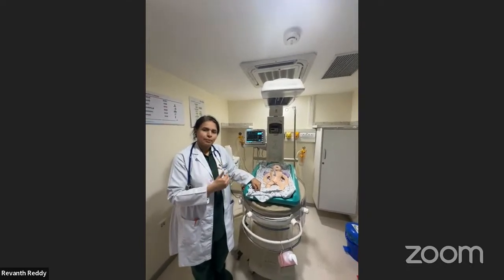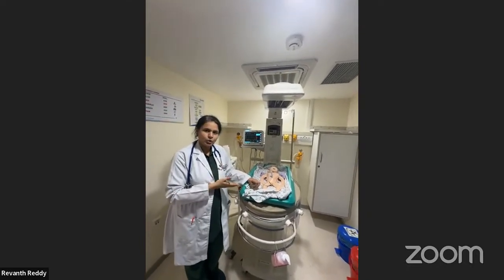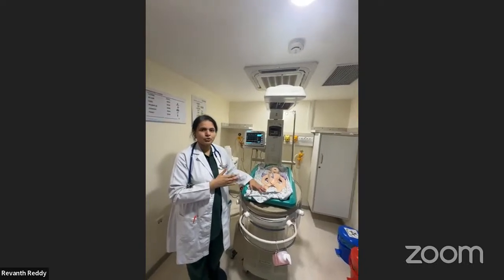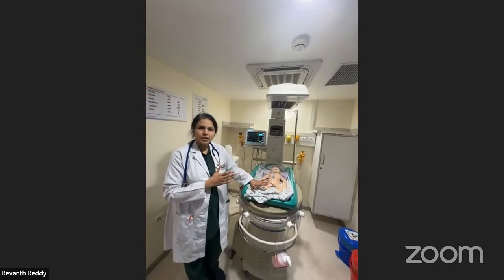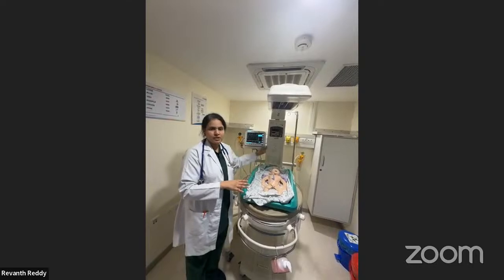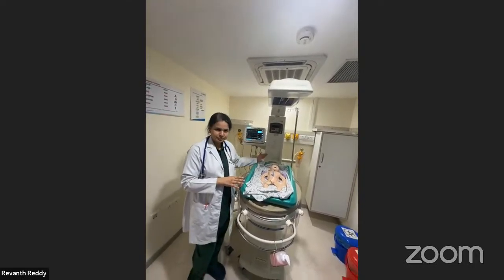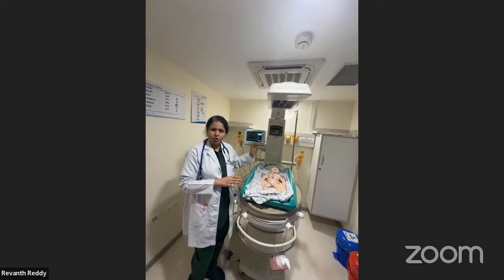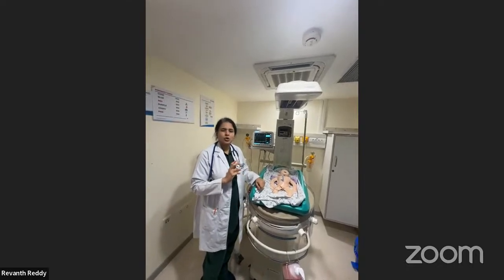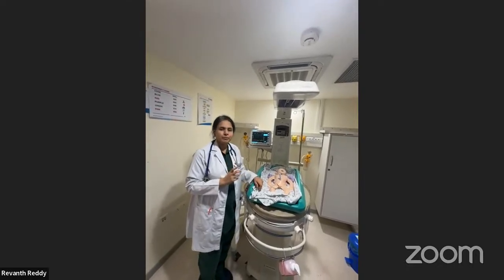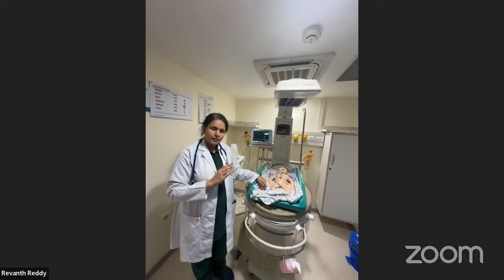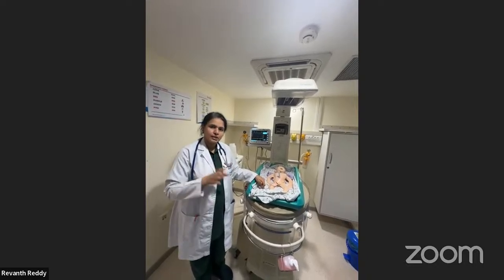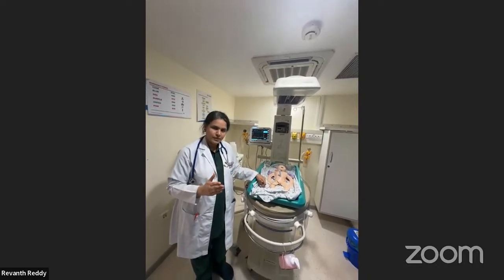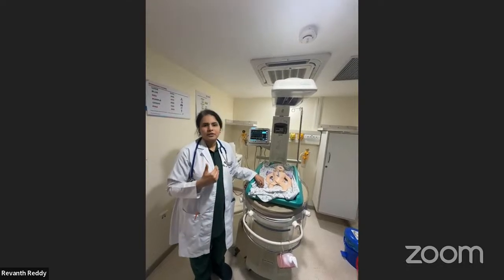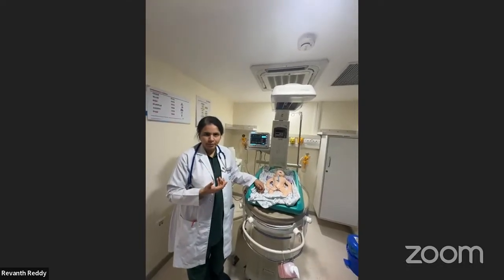Supposing the temperature is dropping too low, going to less than 33 degrees Celsius, what do we do? We don't immediately change the mattresses, but we just switch on the radiant warmer and place the radiant warmer heater output at around 10 or 20 degrees output in manual mode. Allow the temperature to gradually reach the target temperature of 33 to 34 degrees Celsius, and then we shall switch off the radiant warmer.